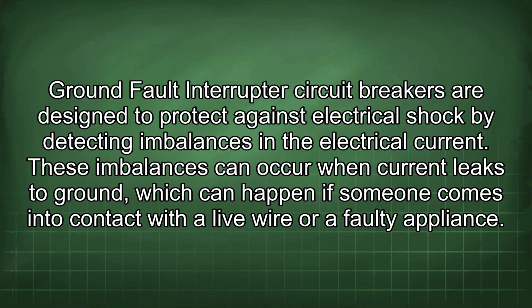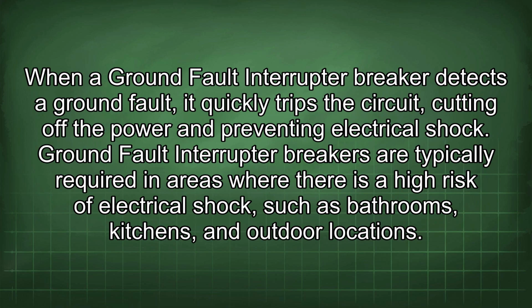Ground fault interrupter circuit breakers are designed to protect against electrical shock by detecting imbalances in the electrical current. These imbalances can occur when current leaks to ground, which can happen if someone comes into contact with a live wire or faulty appliance. When a ground fault interrupter breaker detects a ground fault, it quickly trips the circuit, cutting off the power and preventing electrical shock.